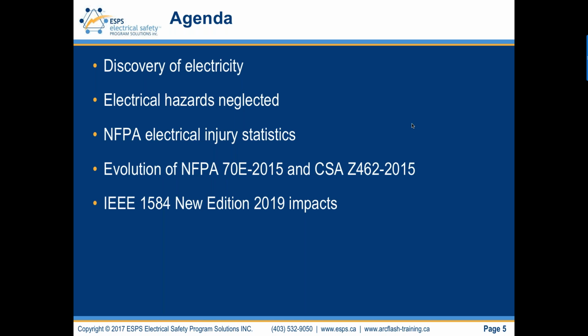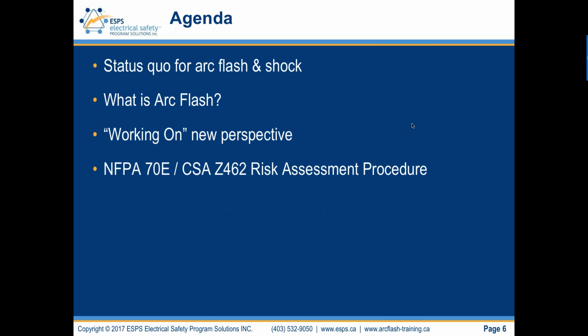Not much detail there, but the new edition, at this point possibly 2019, I sure hope that it publishes then. It's being balloted as we speak. So internal IEEE processes, issues with the balloting, we'll see what happens. But there's going to be some changes there that will need to be managed by industry, or else we're going to have a significant problem with arc flash incident energy analysis studies.